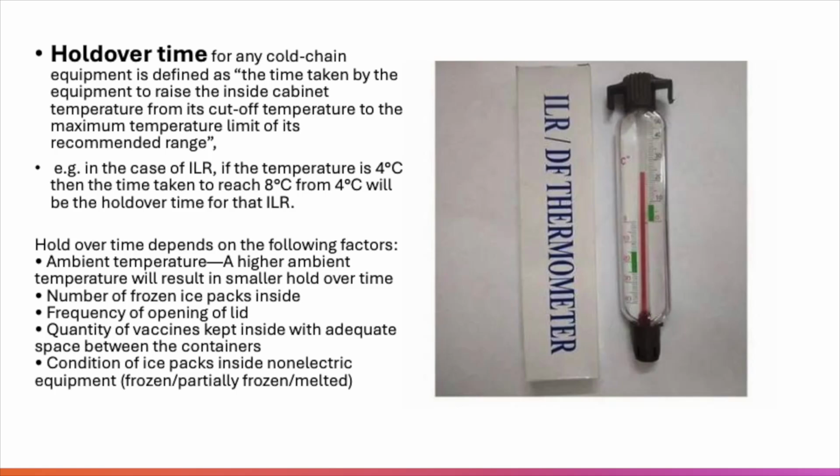Holdover time depends on several factors. First, ambient temperature, where a higher ambient temperature results in a smaller holdover time. Second, the number of frozen ice packs inside the equipment. Third, the frequency of opening the lid. Fourth, the quantity of vaccines kept inside with adequate space between the containers. And fifth, the condition of the ice packs inside non electric equipment, whether they are frozen, partially frozen, or melted.